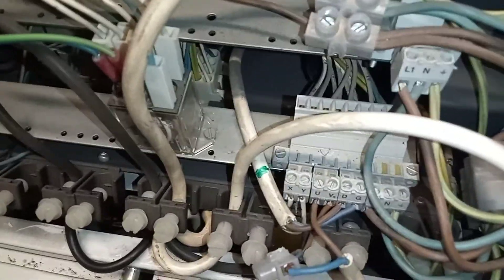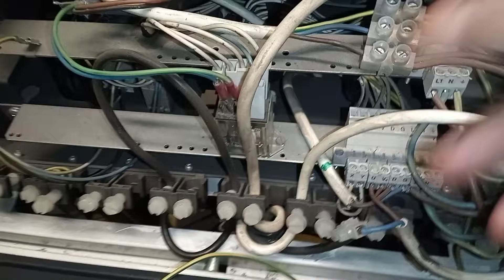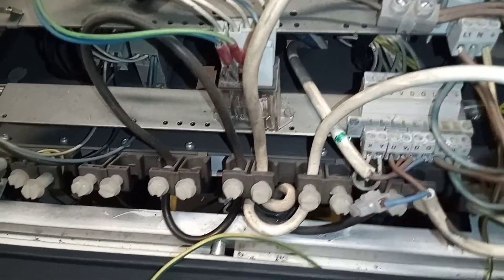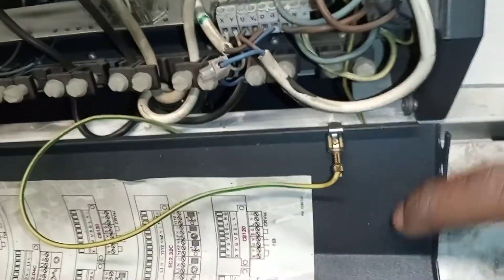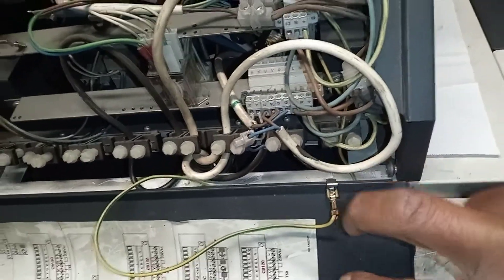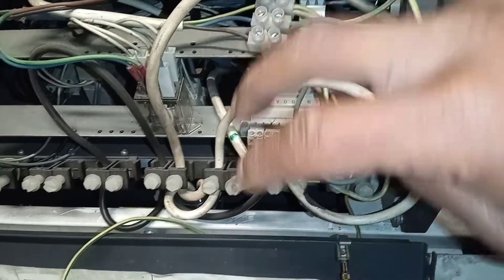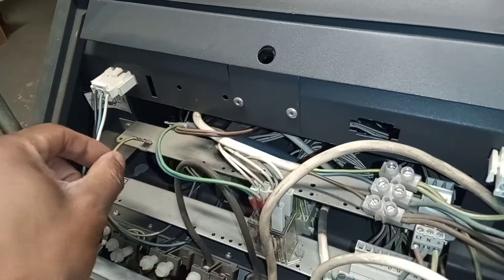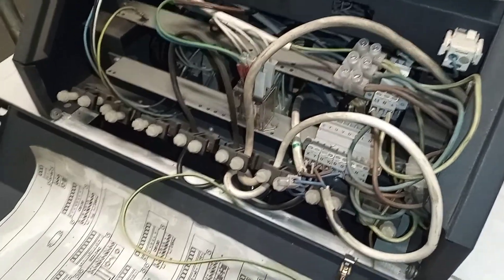Next I went to the wiring — checking for continuity. I went to the back of the boiler, turned the power off, and did my safe isolation. Then I checked my terminals and went round making sure everything was tight. I did find a loose connection on one of my wires and put that back into place. I then inspected wires more thoroughly, did continuity tests with the beep indicator, checked earth connections, and looked for any damage.